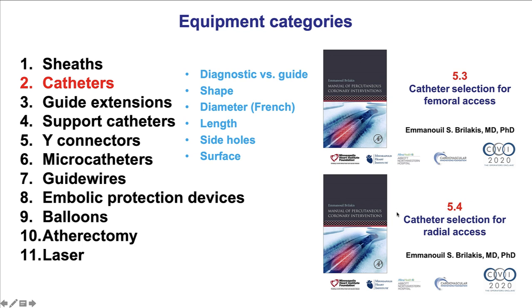Next are the catheters, essential for performing Percutaneous Coronary Intervention. There are diagnostic catheters and guide catheters, with diagnostic catheters having thicker walls and as a result a smaller lumen compared with guide catheters. There are various shapes and diameters, ranging between 4 to 6 French for diagnostic and 5 to 8 French for guide catheters. There are various lengths, with the standard being 100 centimeters, but shorter lengths for retrograde CTO PCI — for example 90 cm — as well as longer lengths such as 125 cm for very tall patients or those with aortic tortuosity. Some guides have side holes and some have a dimpled surface, such as the IKARI guides used via radial access, discussed in videos 5.3 and 5.4.